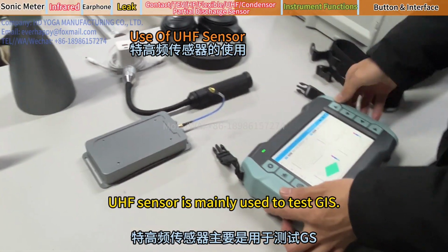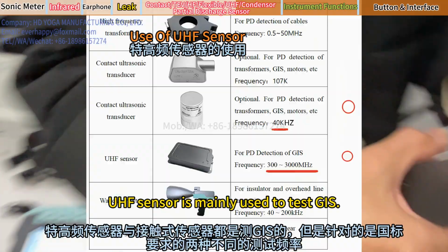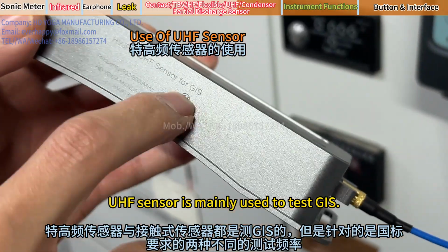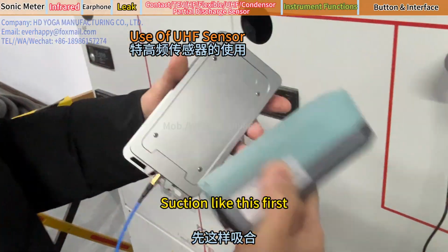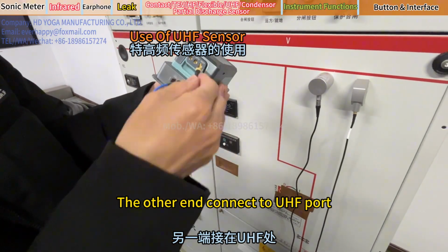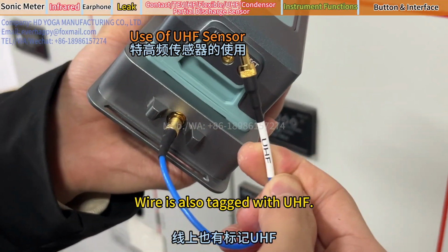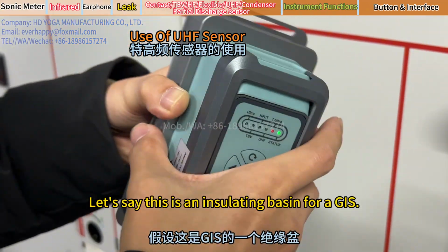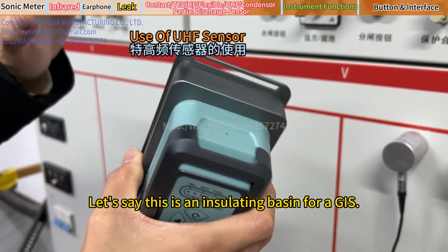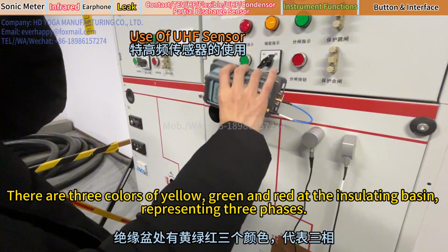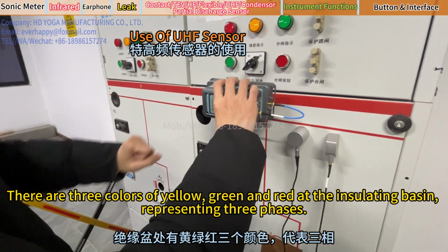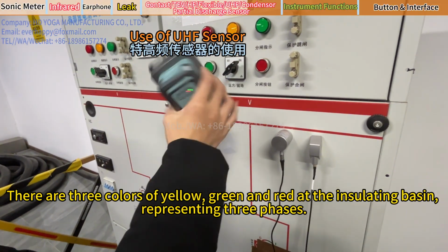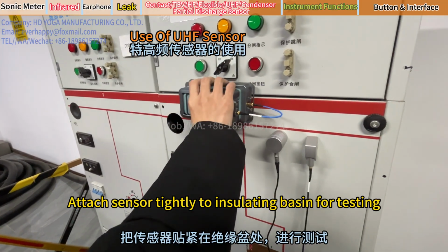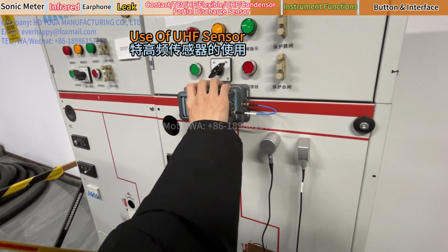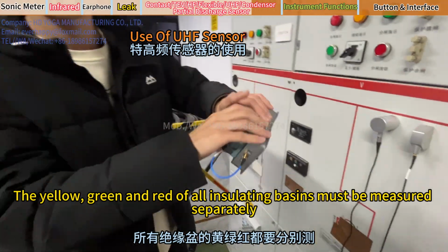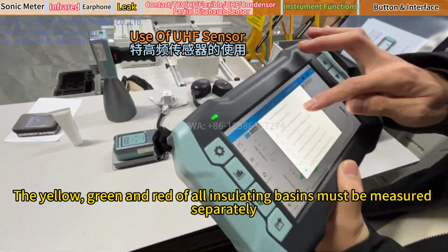The UHF sensor is mainly used to test GIS. Attach the suction end like this first, and connect the other end to the UHF port. The wire is also tagged with UHF. Let's say this is an insulating basin for a GIS. There are 3 colors of yellow, green, and red at the insulating basin, representing 3 phases. Attach the sensor tightly to the insulating basin for testing. The yellow, green, and red of all insulating basins must be measured separately.